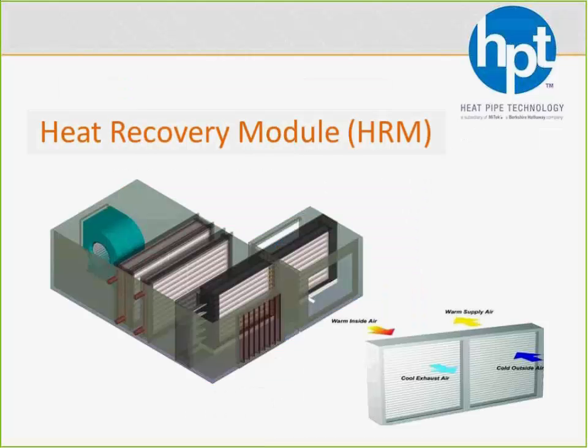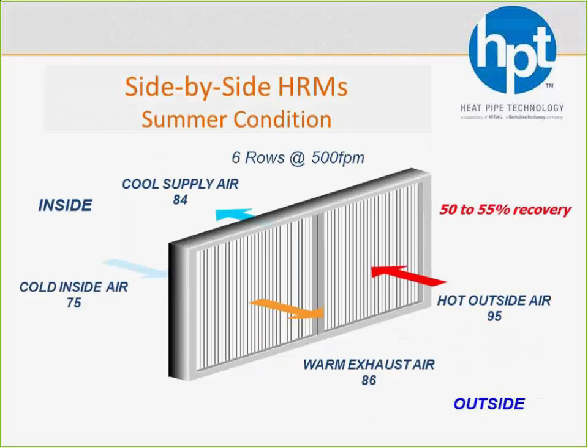So for heat recovery, our heat recovery module is aptly named the HRM. And it's basically used to take heat from one side to move it to the other side. So in the summertime, we're going to take that hot outside air and we're going to pre-cool it by dumping that heat into the cool.